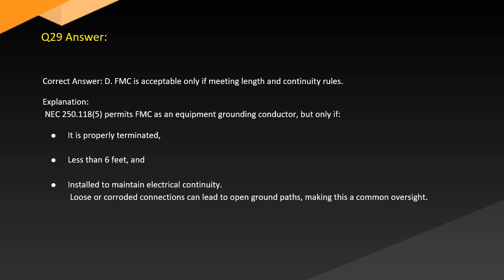Answer. Correct answer: D. FMC is acceptable only if meeting length and continuity rules. Explanation. NEC 250.118(5) permits FMC as an equipment grounding conductor, but only if it is properly terminated, less than 6 feet, and installed to maintain electrical continuity. Loose or corroded connections can lead to open ground paths, making this a common oversight.